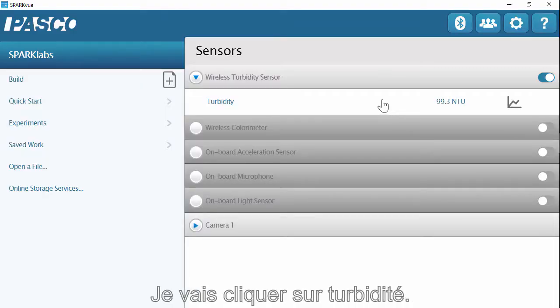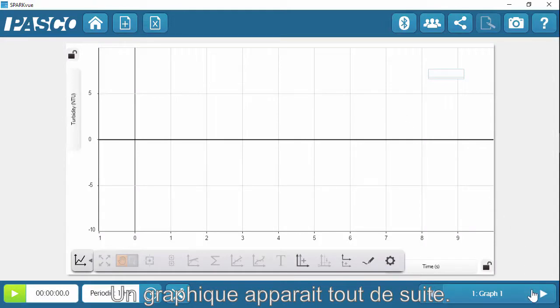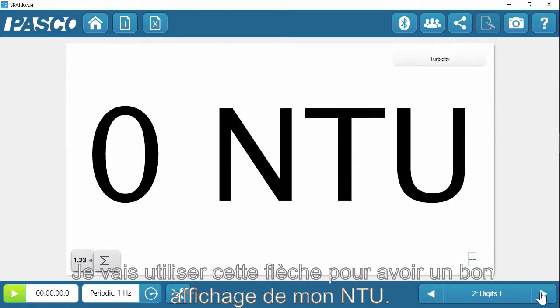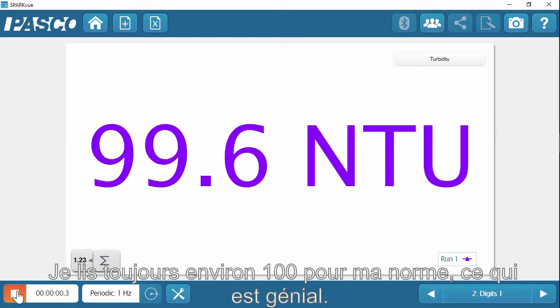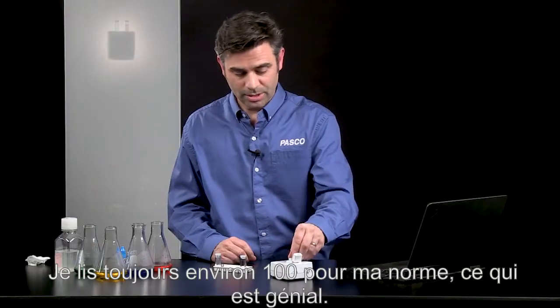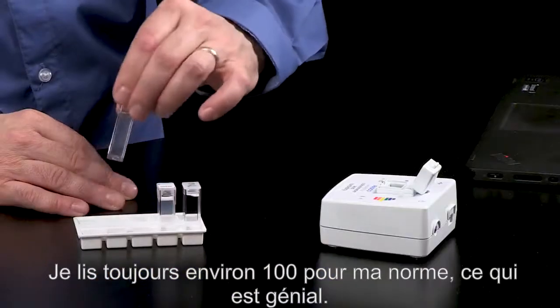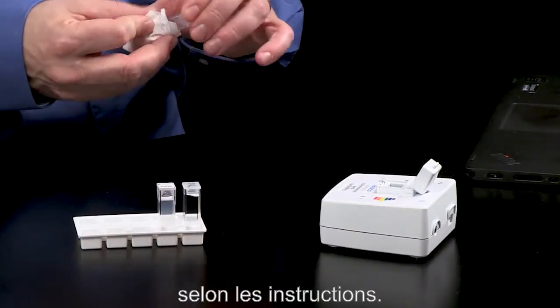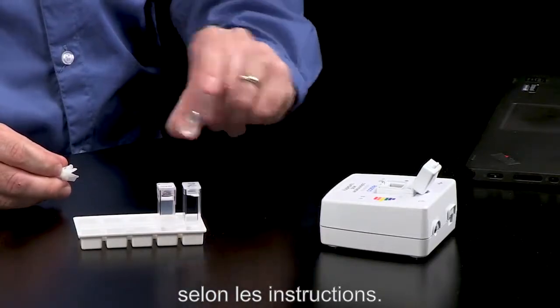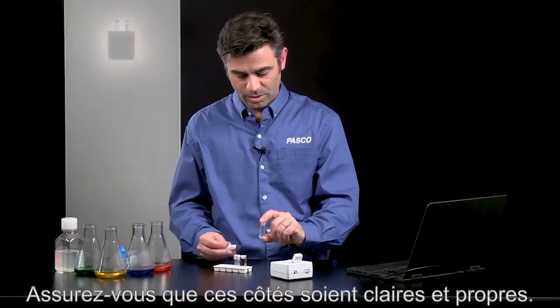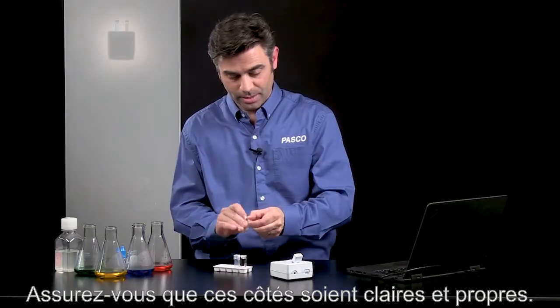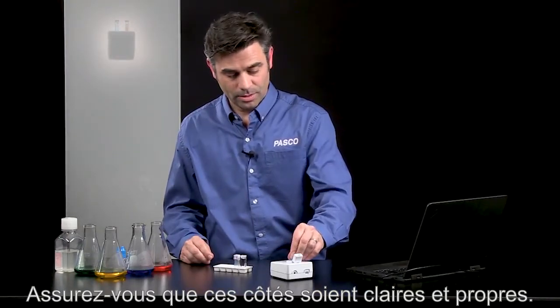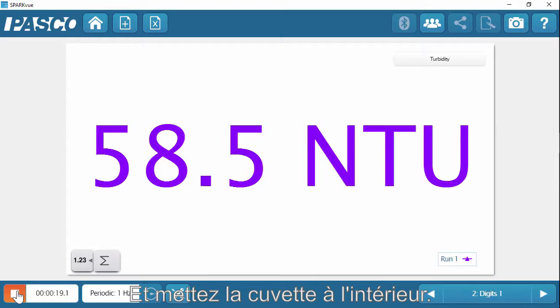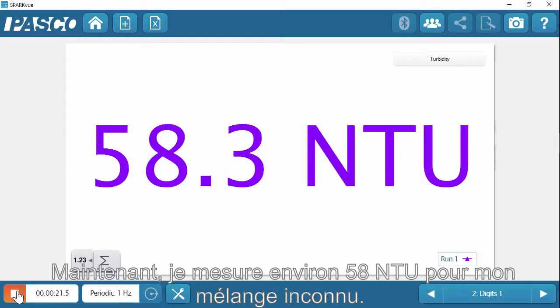So I'm going to click on turbidity. I get a graph right away. It's going to use this arrow to have a nice big display of my NTU. I'm still reading about 100 for my standard, which is great. I'm going to, again, make sure this is nice and mixed according to the instructions. Make sure those sides are clear and clean. Put that in. And now I'm measuring about 58 NTUs for my unknown.